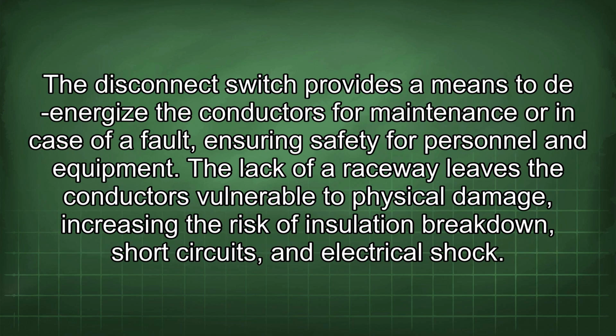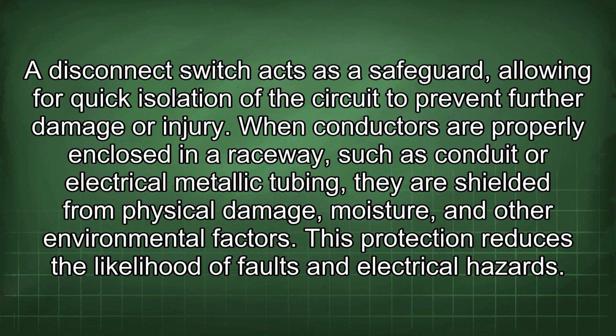The disconnect switch provides a means to de-energize the conductors for maintenance or in case of a fault, ensuring safety for personnel and equipment. The lack of a raceway leaves the conductors vulnerable to physical damage, increasing the risk of insulation breakdown, short circuits, and electrical shock. A disconnect switch acts as a safeguard, allowing for quick isolation of the circuit to prevent further damage or injury.